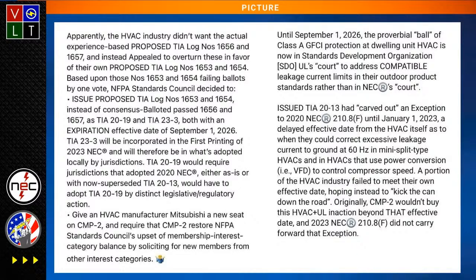First, let me teach you something on this. The person who wrote this, the NEC does not dictate how the HVAC equipment is designed. It's a listed and labeled piece of equipment by UL, and for you to make this type of statement, that it's out of the NEC's court, I'll tell you what you did. You tried to dictate something to a piece of equipment that wasn't compatible, and now you're saying the proverbial ball got kicked down the road. It didn't get kicked down the road. It got put at the spot it was meant to be in the first place, taking it out of the hands of code-making panel 2, because of an unbiased group that put something together requiring GFCI protection that didn't need it. That's what that means.